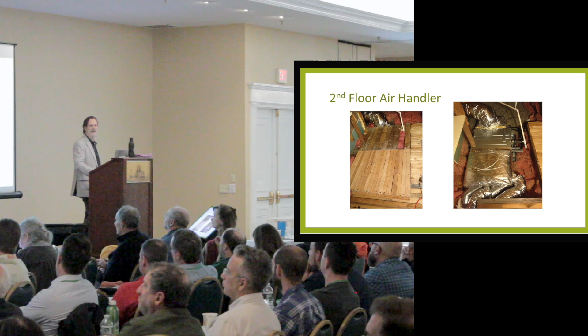The second floor system, the second zone of the 2-zone system, is ducted. And so there's a little air handler in the attic, which has a pile of insulation on top of it that's hiding under those floorboards on the left. So not a fantastic job. But considering I added them after the house had been built, I did the best I could. Examples of what one of the outdoor units looks like. And the basic upshot of all this is I measured everything. I did an electric co-heat test in the house to see what the actual heating load was. And the measured COP was around 2.8, which is actually pretty good for the climate that I live in.